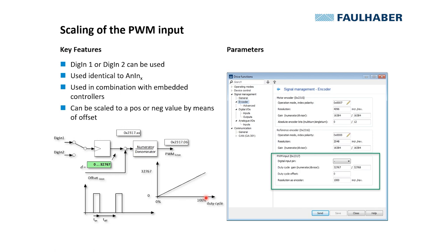As a PWM signal is essentially having 0% to maximum of 100%, that's the scaling here. So we do get the input range of the duty cycle and that's the internal numeric range here, so we are counting 15 bit up to 32,767 counts here.